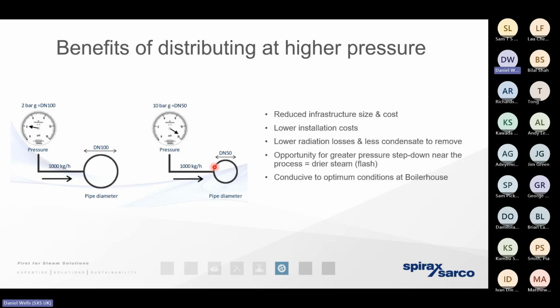So if we're putting 10,000 kilograms of steam out of the boiler into the pipework, we're far more likely to be getting closer to 10,000 kilograms of steam out the other end. The boiler doesn't have to work as hard. We're not consuming as much gas. The cost of steam and those carbon emissions are going to fall. Other benefits are if we've got drier steam and we don't have as much condensate sloshing about in the pipes, we're not going to need as many steam traps. So we're reducing the capital cost further still. And we've reduced the risk that those steam traps could fail in the open position. So we're helping to safeguard against those losses and inefficiencies.